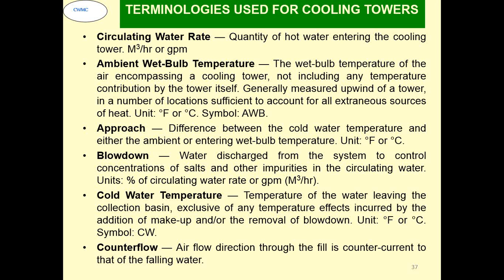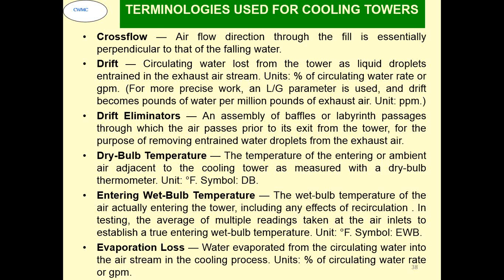Counterflow, airflow direction through the fill is counter current to that of the falling water. Cross flow, airflow direction through the fill is essentially perpendicular to that of falling water. Drift is circulating water lost from the tower as liquid droplets entrained in the exhaust air stream. Units are percentage of circulating water or GPM.